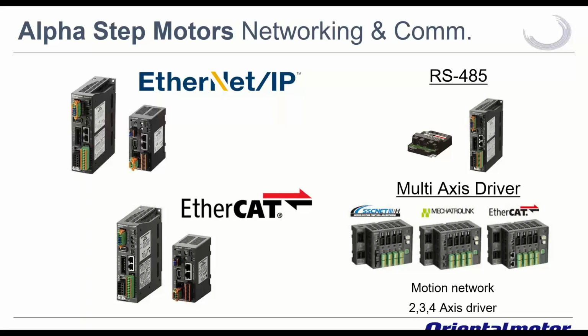In our alpha step system, another thing to call out is the communication and network protocols that are used within the system. As I mentioned before, pulse and direction signals are the common ones in the stepper systems. In alpha step, we also have drivers that communicate specifically for network communication, such as Ethernet IP and EtherCAT. There's also RS-485 drivers and some multi-axis drivers that facilitate SSCNet, Mechatrolink, and EtherCAT. So depending on what type of upper level control or what PLC is there, there's a driver that can be paired with that upper level of control.